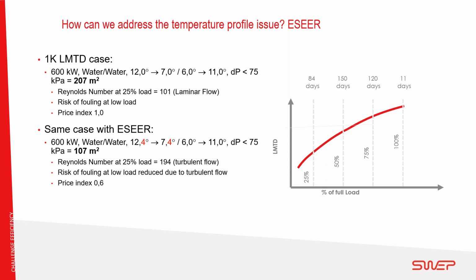So how can we address the temperature profile issue? Increasing the LMTD not only allows for a smaller heat exchanger to be used, but also allows for higher channel velocities and hence better performance and reduced risk of fouling. Since the heat exchanger is designed for peak load conditions, which may rarely be experienced, it may be beneficial to apply load profiling, such as the European Seasonal Energy Efficiency Ratio. Applying such load profiles to the selection of the heat exchanger adapts the LMTD for the peak load design condition to give a heat exchanger with less surface area. The effects can be highly beneficial, reducing capital costs and operating costs, since the heat exchanger will be smaller and provides turbulent conditions for a greater period of the year.